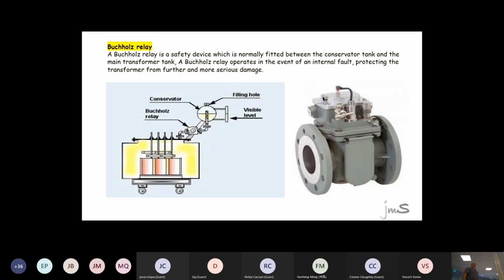Right. Don't do this at home. I'll repeat, don't do this at home at all. But if you take phase and neutral and you put it in water, is it true that you can boil the water? Yep. Right. Don't do this at home. But anyway, if you take phase and neutral and you short it out inside water, what does it make? Arc? Yes. But what does it give off? Heat. Yes, but also bubbles. Now any transformer, if the windings start scratching to the earth or scratching against each other, and this arcing, that bubbles will be detected inside the Buchholz relay. And the Buchholz relay will either switch an alarm on or even switch the transformer off. It depends on the severity of that fault inside it.